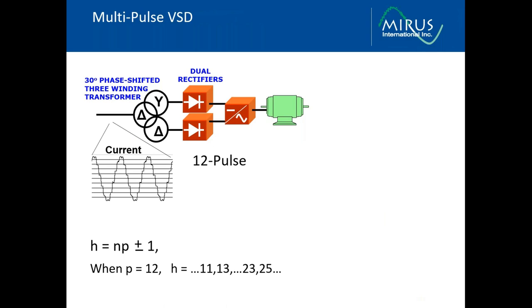Multipulse VFDs utilize multiple rectifiers that are phase shifted with transformers to cancel harmonics. So a 12 pulse system is going to have two three phase six pulse rectifiers, which are phase shifted by 30 degrees. So in this example, we've got a delta transformer, which would introduce a zero phase shift, and then a delta Y connection, which would introduce a 30 degree phase shift. When you do that, the fifth and seventh harmonics predominantly are canceled, ideally, in a theoretical way. And the resultant harmonics that we'll see are the 11th, 13th, 23rd, and 25th harmonics. So this is an ideal arrangement.